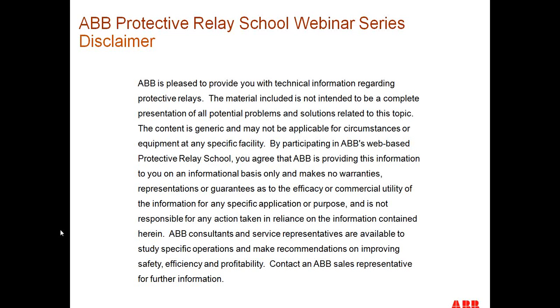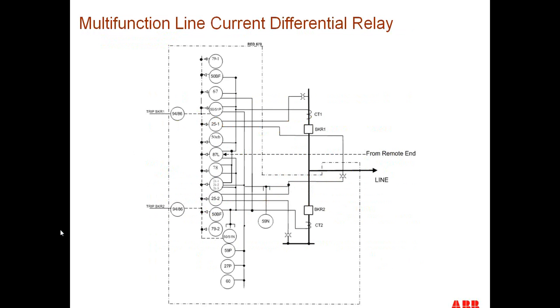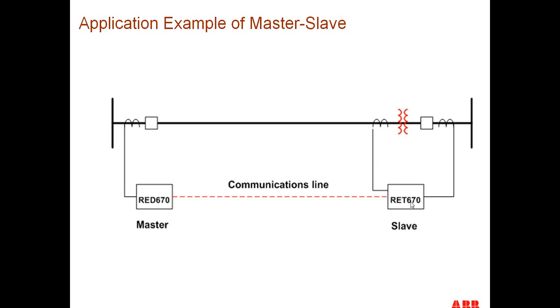Another question came up: is your RED able to talk to the RET in the line differential mode? Yes, the RED 670, in that example I showed a while back, is talking to the RET 670 and exchanging information with it. And it's actually one-way communication. The RET sends its line data to the RED 670. It does the analysis, and if it calls for a trip, it sends a trip back to the RET that trips the breaker.